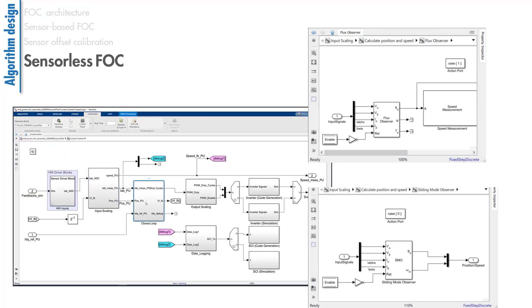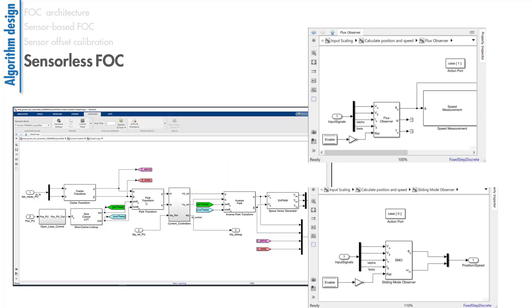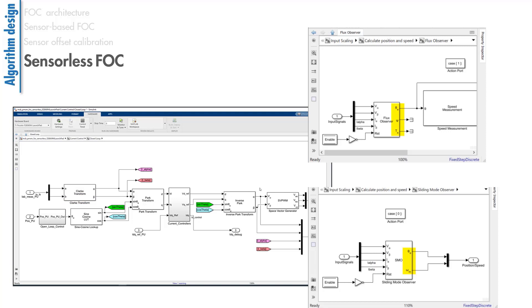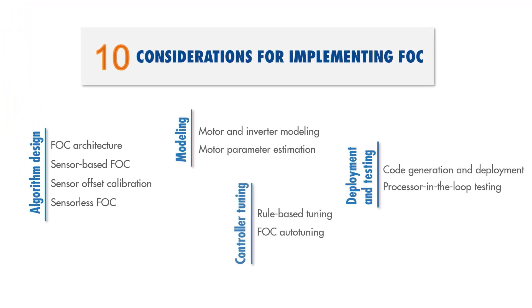Recall that these voltages and currents were computed by these transforms in the current control section of the FOC algorithm. Similarly, if we now navigate to current control in this example, we see that the inputs to the observer blocks are the voltages computed by the inverse Park transform and the currents computed by the Clarke transform. The observers then output the estimated rotor position of the motor and other estimated values such as the rotor flux and torque.